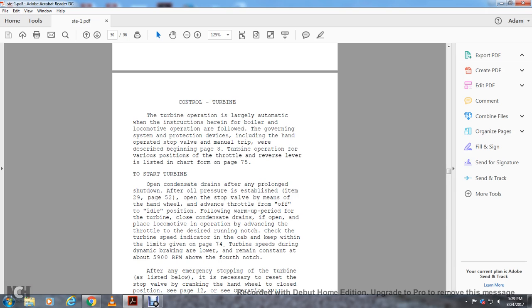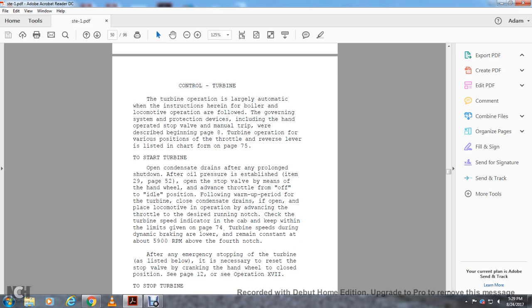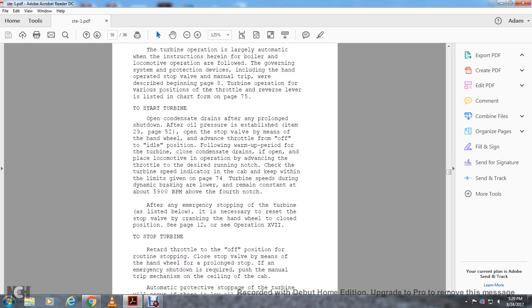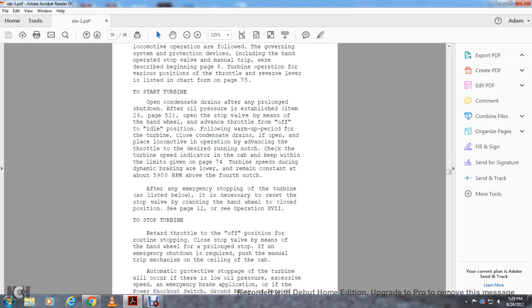Turbine speeds during dynamic braking are low, but remain constant at 5,900 RPM above the fourth notch. After an emergency stopping of the turbine, it is necessary to reset the stop valve by cranking the hand wheel to the close position. See page 12, or see Operation XVII. To stop the turbine, retard the throttle to the off position.